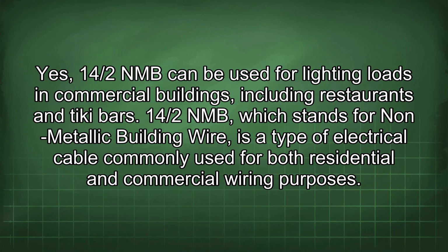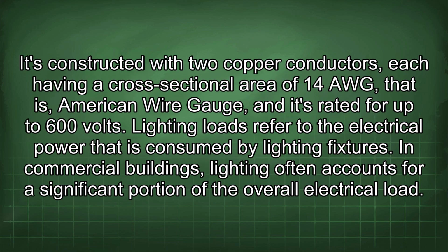Yes, 14/2 NMB can be used for lighting loads in commercial buildings, including restaurants and tiki bars. 14/2 NMB, which stands for non-metallic building wire, is a type of electrical cable commonly used for both residential and commercial wiring purposes. It's constructed with two copper conductors, each having a cross-sectional area of 14 AWG, that is, American wire gauge, and it's rated for up to 600 volts.